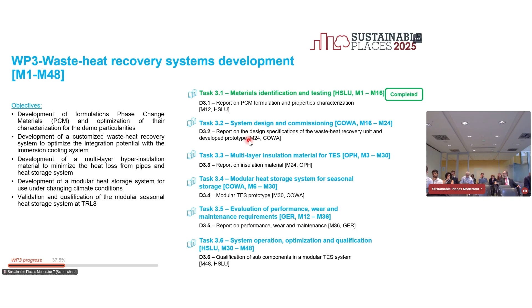What I'll go into now is what we are mainly working on: the material studies we have done. This is a 4-year project, and we're now halfway through, having delivered our first report at the end of last year on the material development and testing of these new phase change materials. These should be applicable within a temperature range of 40 to 60 degrees, which is what's allowed for operating an immersion cooling unit. I'll also look a bit into the next task, due at the end of this year, which is the system design: how we design the immersion cooling unit connected to the PCM storage and how it is operated.